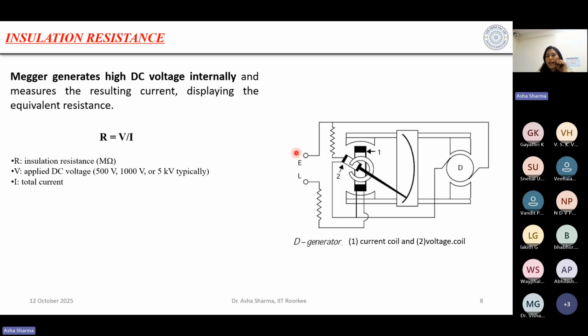This is the diagram of the megger. In the megger, we have a DC generator that produces some voltage, mostly around 5 kV. There are two coils: the current coil and the potential coil. The current coil produces the deflecting torque, and the voltage coil produces the controlling torque.